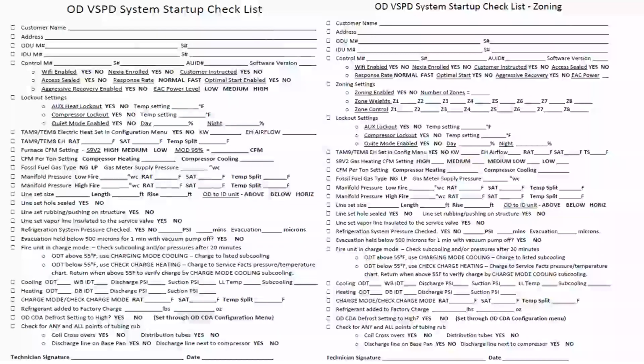If anybody wants copies of our variable speed startup sheet or the zoning one, again, this is something we ask for if we do have an issue after the installation startup. I'm going to ask for a startup sheet, because we're going to submit it to factory. We want to verify that the system has been started up within parameters. So if we do have a failure 6 months down the line, was it started up correctly? Is there an overcharge? What was the subcooling? We can tell a lot from that data.